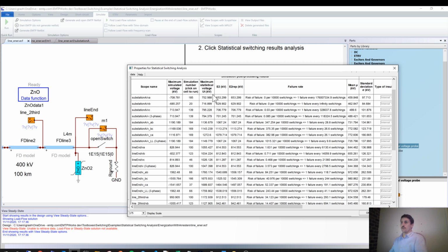Then you have the maximum statistical voltage, UT, which has several names: truncature voltage, truncature overvoltage, or maximum assumed overvoltage. This one is statistically calculated. You see that typically it's higher than the first one, but it's not necessarily the case, because it's statistical. If you do many simulations, those two should be very close. But if you don't do enough simulations, you may find things which are a bit surprising. Here we see that most of the time it's the case. I see here it's not, but still not so far.